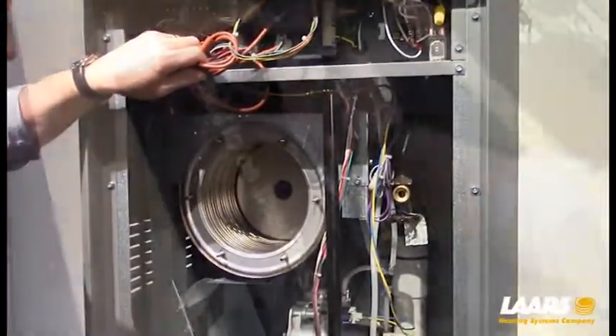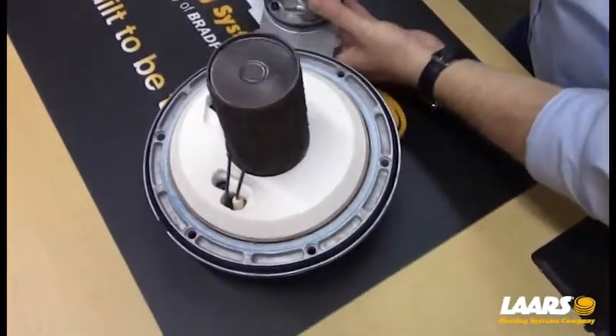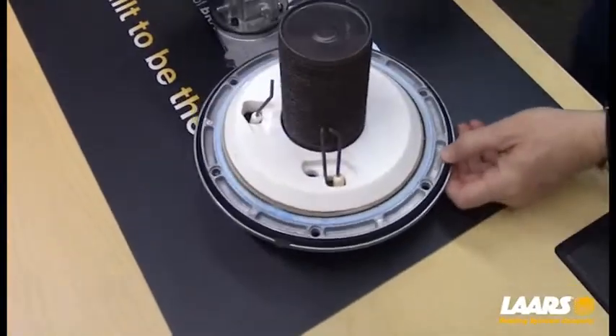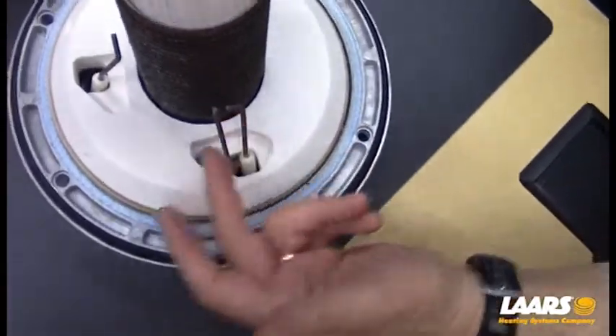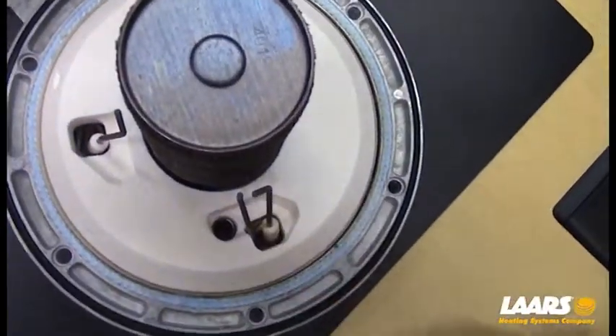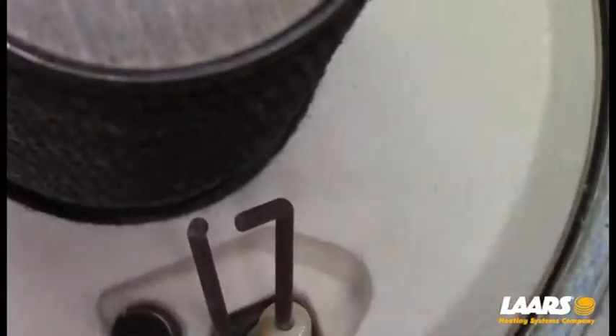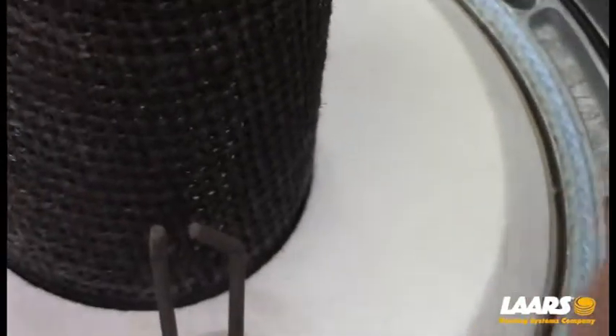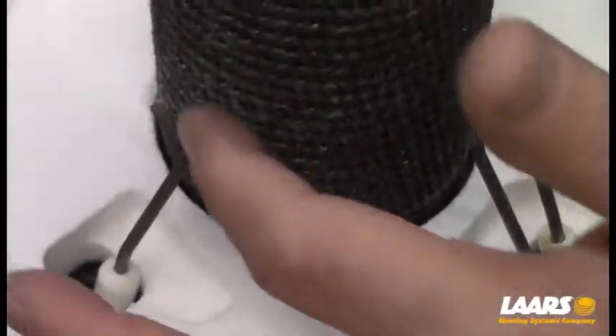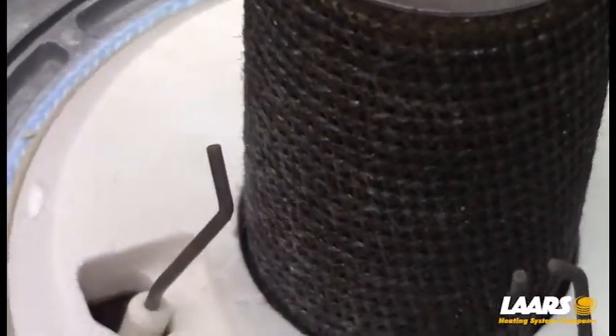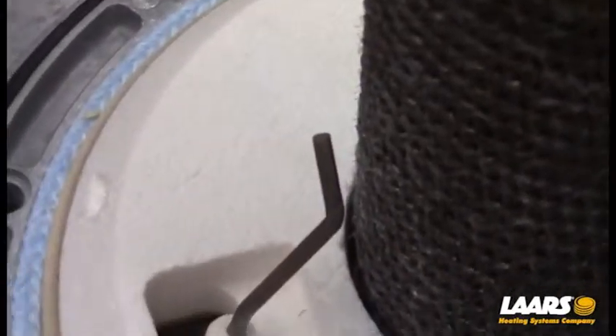Next, we're going to look at the burner. So I'm going to lay this down on its back, and now what we can look at is the gap between the igniter and the flame rod. The igniter gap should be between 3/16 and 1/4 of an inch across the igniter, 1/4 of an inch off the burner head itself. The flame rod should also be 1/4 inch off the burner itself.